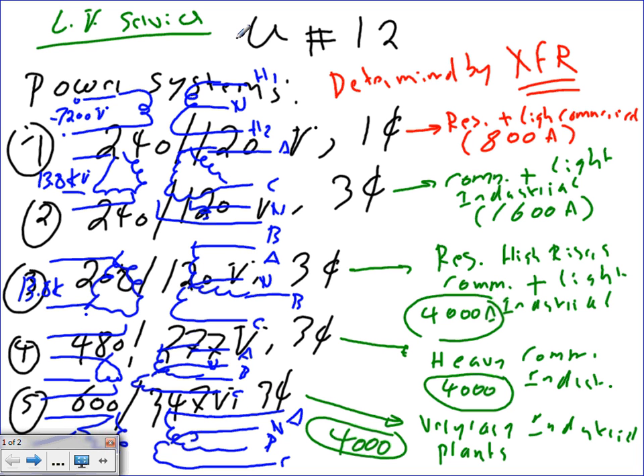Okay, look at the second one, guys. The second one is a delta. I have a delta center tap. Delta. On the primary side, 13.8, 13,800 volt. Utility type, I have no control over it. On the secondary side, that's my baby. I have 240, 120, except it's 3-phase. That's the only time you can get 3-phase 240, 120, is from this type of transformer. That's that bad boy center tap transformer.